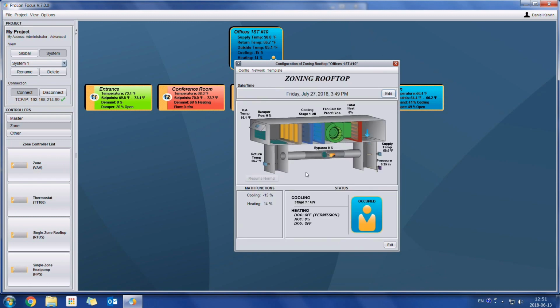The way it's currently configured, it controls the static pressure using a bypass damper. But what if we don't have a bypass damper? What if instead we have a variable frequency drive? Well, we would like to change that.